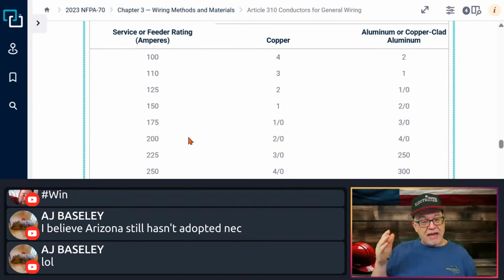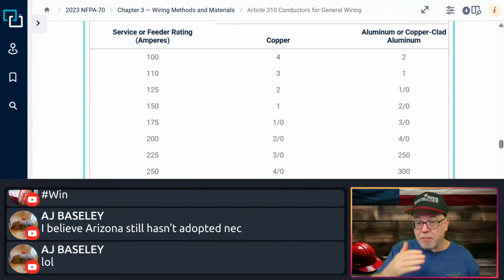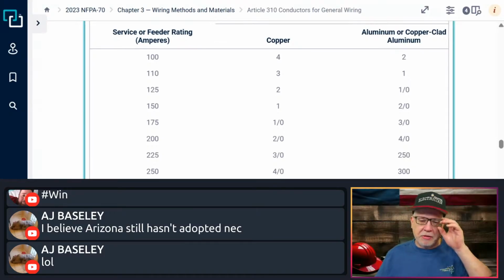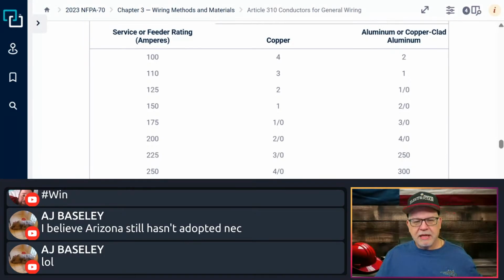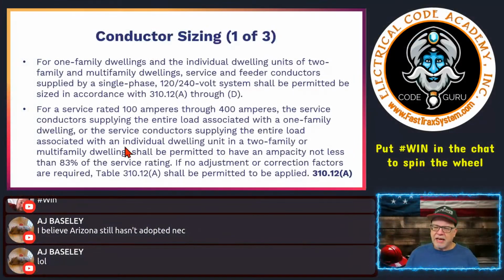At the end of the day, after the adjustment or correction, you still have to make sure you have a conductor that is not less than what? 83% of the service or feeder rating, okay? Very important to still remember that. The 83% doesn't go away if you want to use this rule. Now, can you ignore this and just size it based on 310.16? Absolutely, you can. If that's your prerogative, you most certainly can.